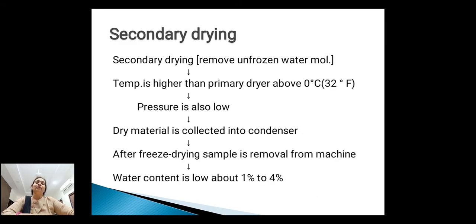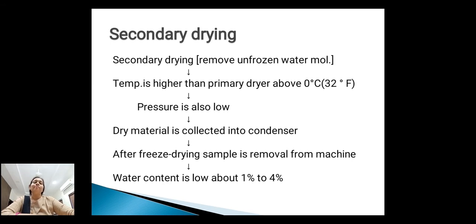Next, secondary drying, which removes unfrozen water molecules. The temperature is higher than in primary drying — above 0 degrees centigrade or 32 degrees Fahrenheit — and pressure is also low. Dry material is collected into the condenser. After freeze drying, the sample is removed from the equipment. At the end of the process, the water content is low, about 1 to 4 percent.